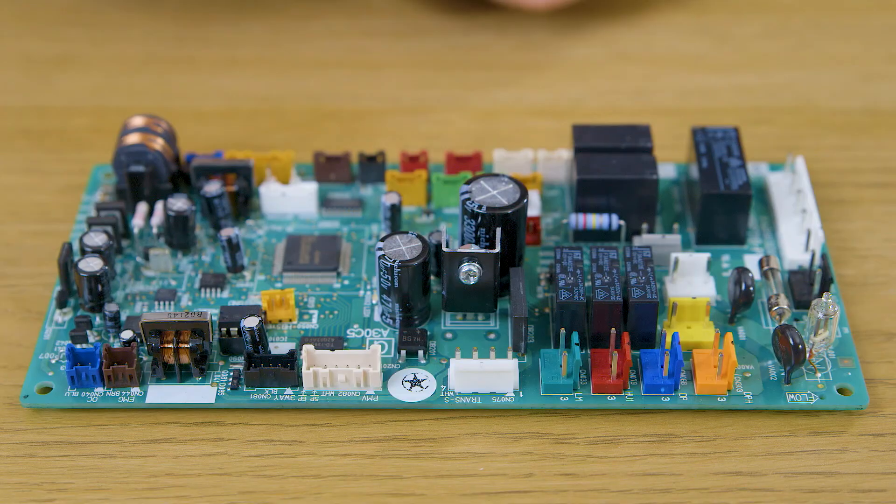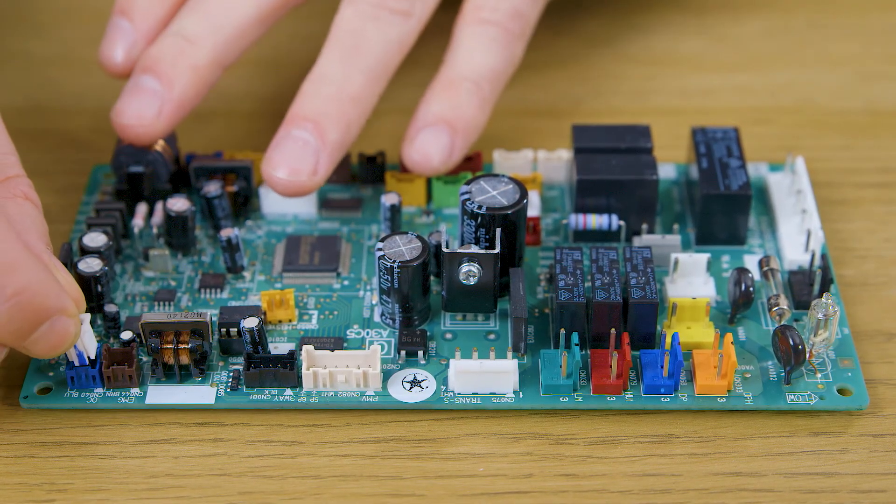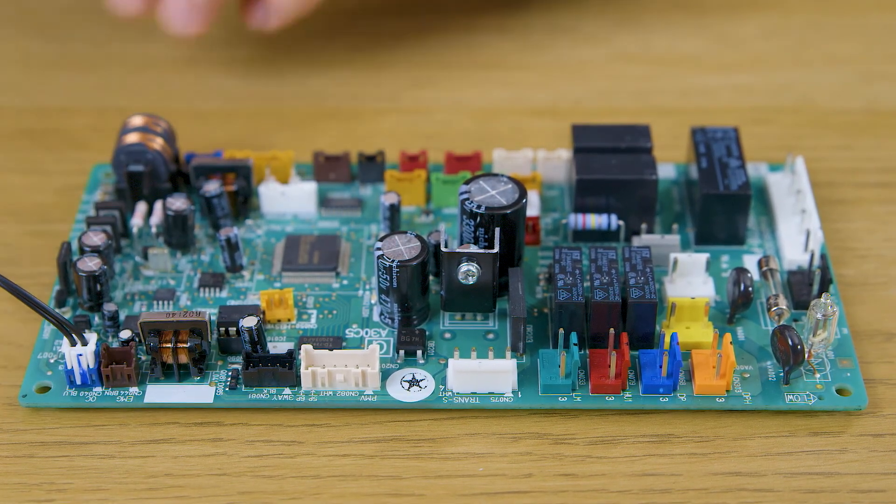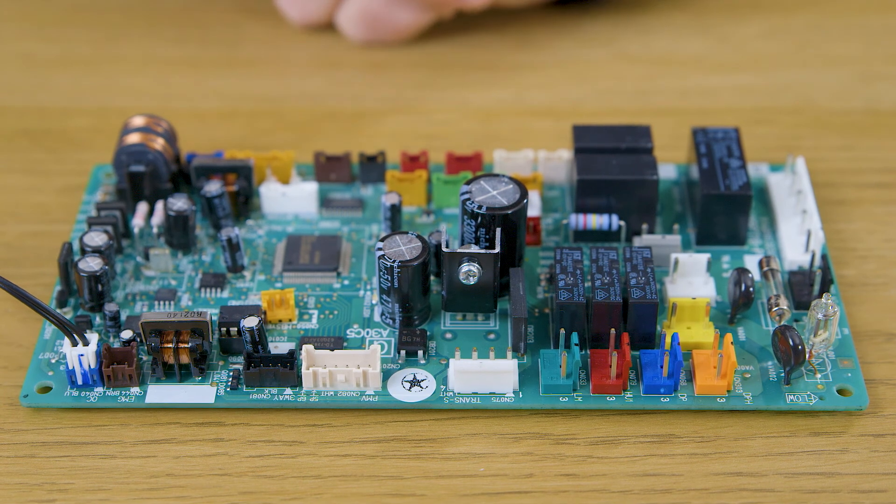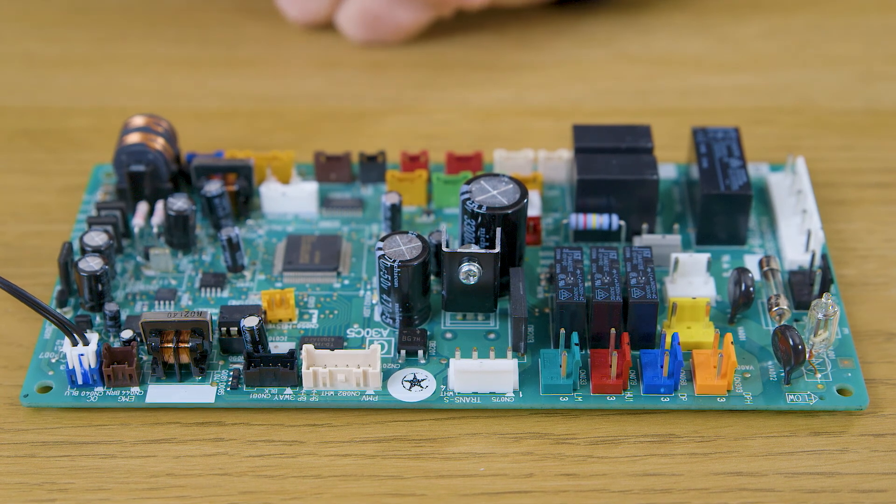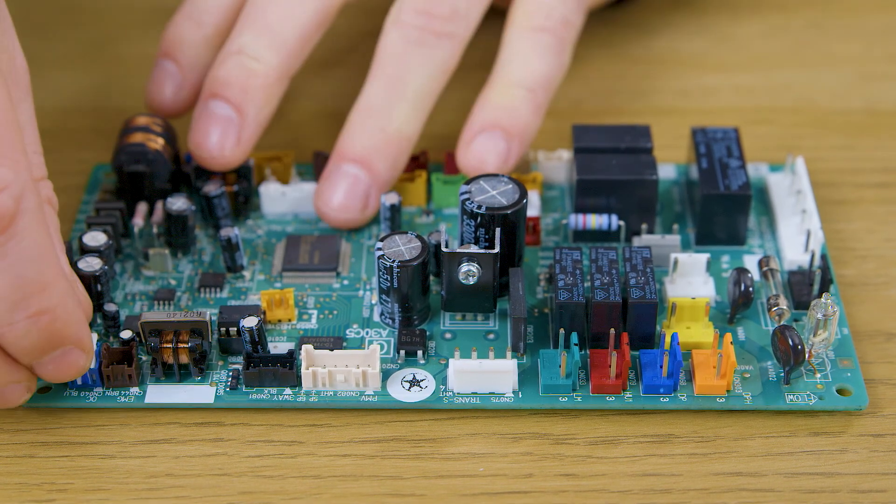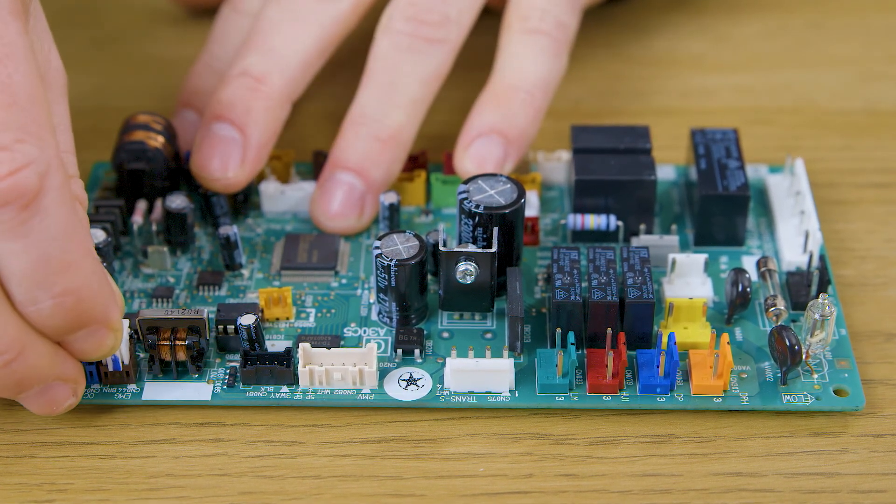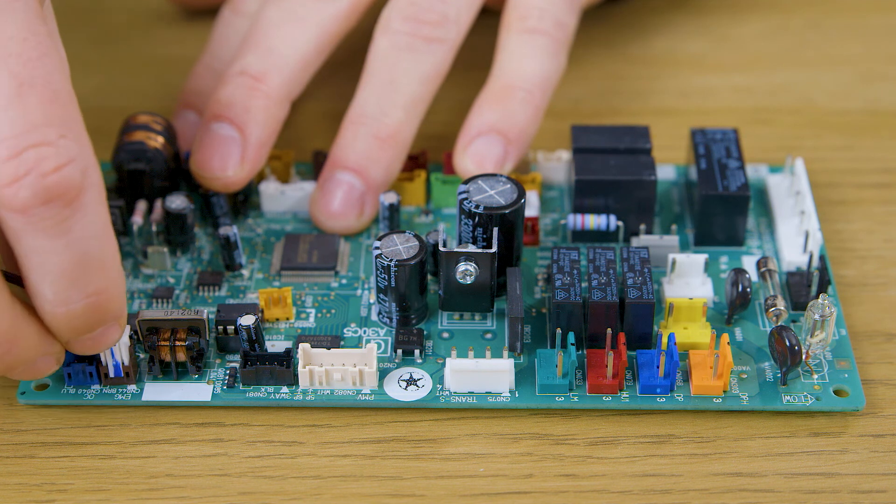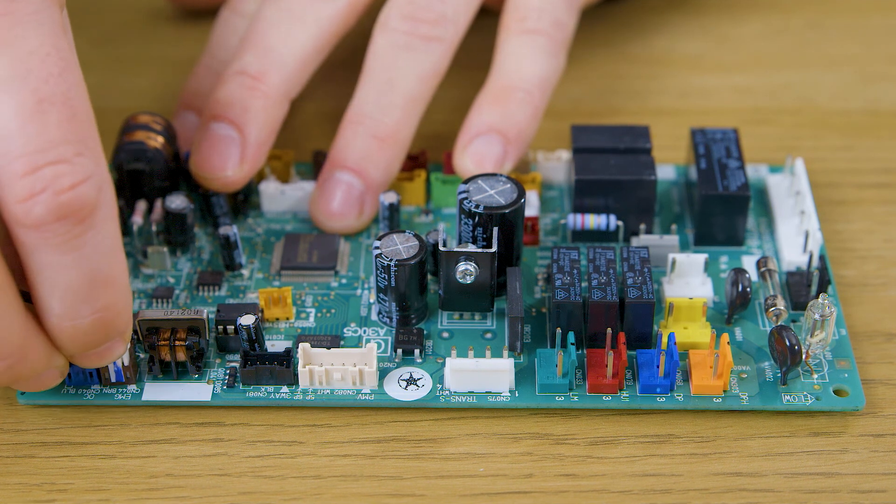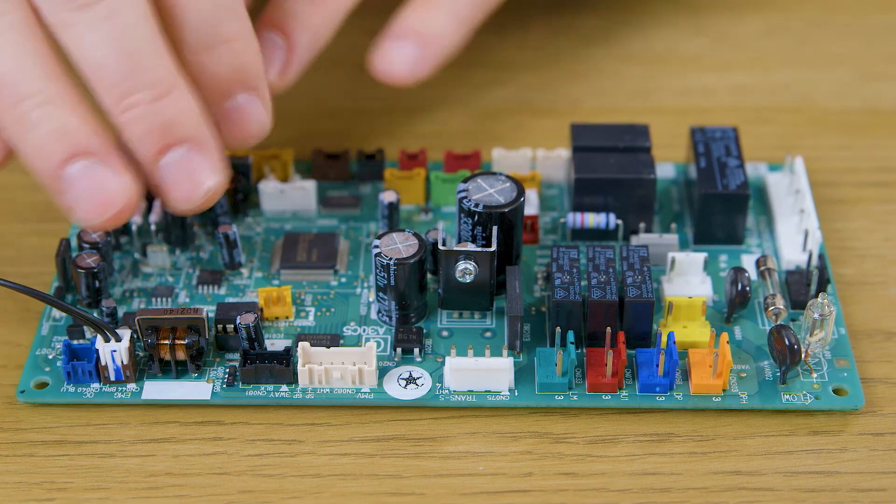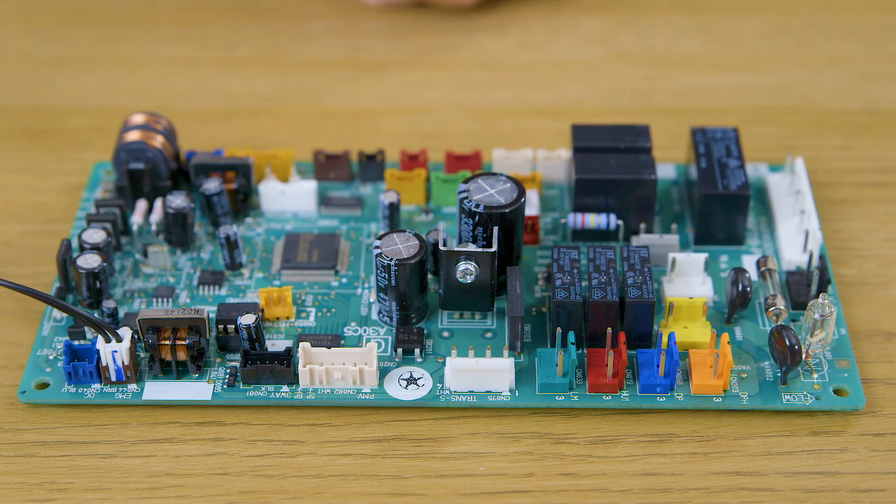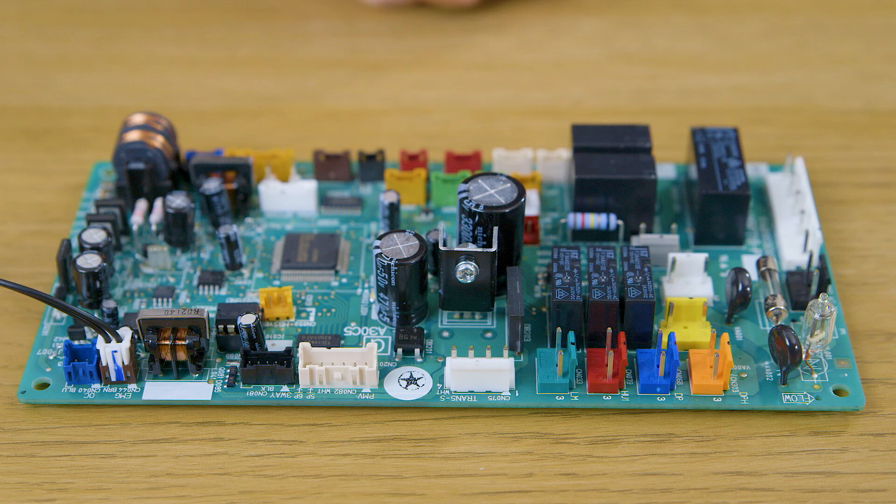On the indoor PCBs we have the same principle - a blue OC plug where the U1, U2 plugs into. If that has failed, simply unplug and plug into the brown connection next to it which says EMG, stands for emergency.